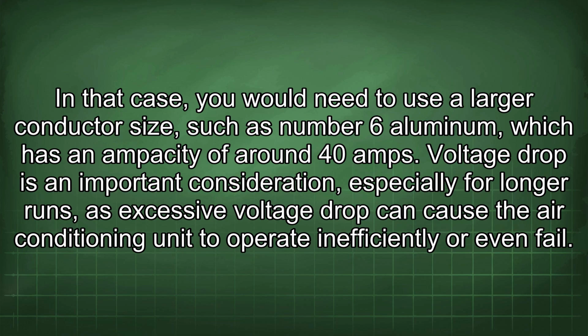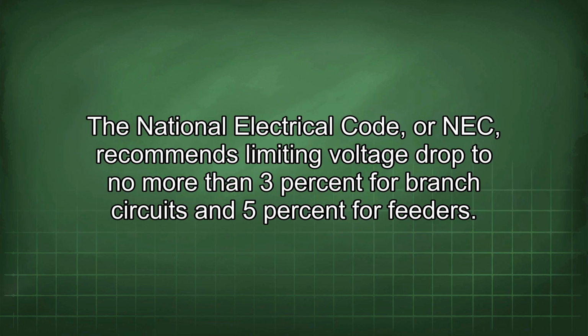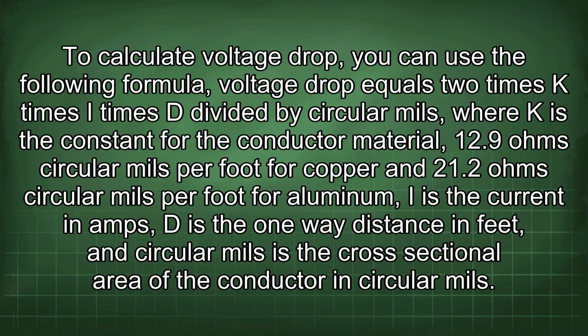Voltage drop is an important consideration, especially for longer runs, as excessive voltage drop can cause the air conditioning unit to operate inefficiently or even fail. The National Electrical Code, or NEC, recommends limiting voltage drop to no more than 3% for branch circuits and 5% for feeders. To calculate voltage drop, you can use the following formula: voltage drop equals 2 times K times I times D divided by circular mils, where K is the constant for the conductor material, 12.9 ohms circular mils per foot for copper and 21.2 ohms circular mils per foot for aluminum. I is the current in amps, D is the one-way distance in feet, and circular mils is the cross-sectional area of the conductor in circular mils.